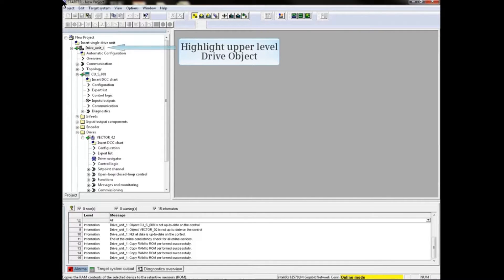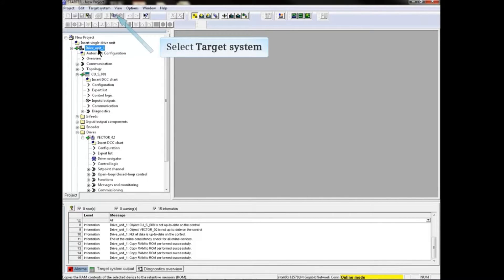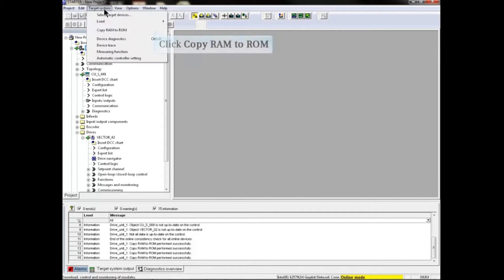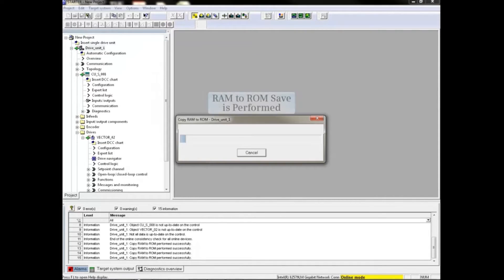Start by highlighting the upper level drive object in the project tree. When the upper level drive object is highlighted, click Target System from the main menu, then click Copy RAM to ROM from the drop-down menu. The RAM to ROM save is performed and a status box appears.